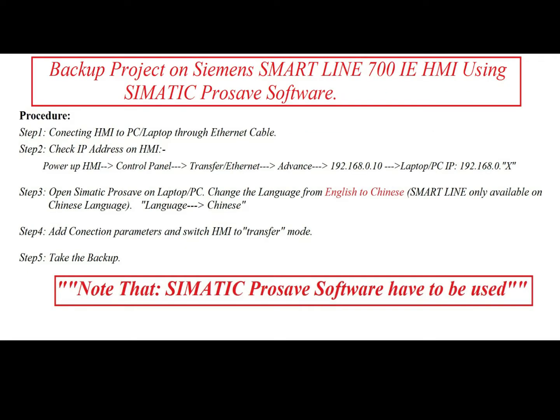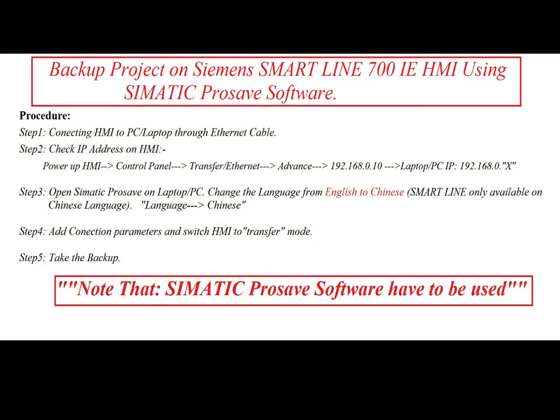The procedure of taking backup from HMI: Step 1, connecting HMI to PC laptop through Ethernet cable. Step 2, check IP address on HMI. Step 3, open Siemens Prosave on laptop, then change the language from English to Chinese because Smartline is only available in Chinese language. Step 4, add the connection parameters and switch HMI to transfer mode, then take the backup.